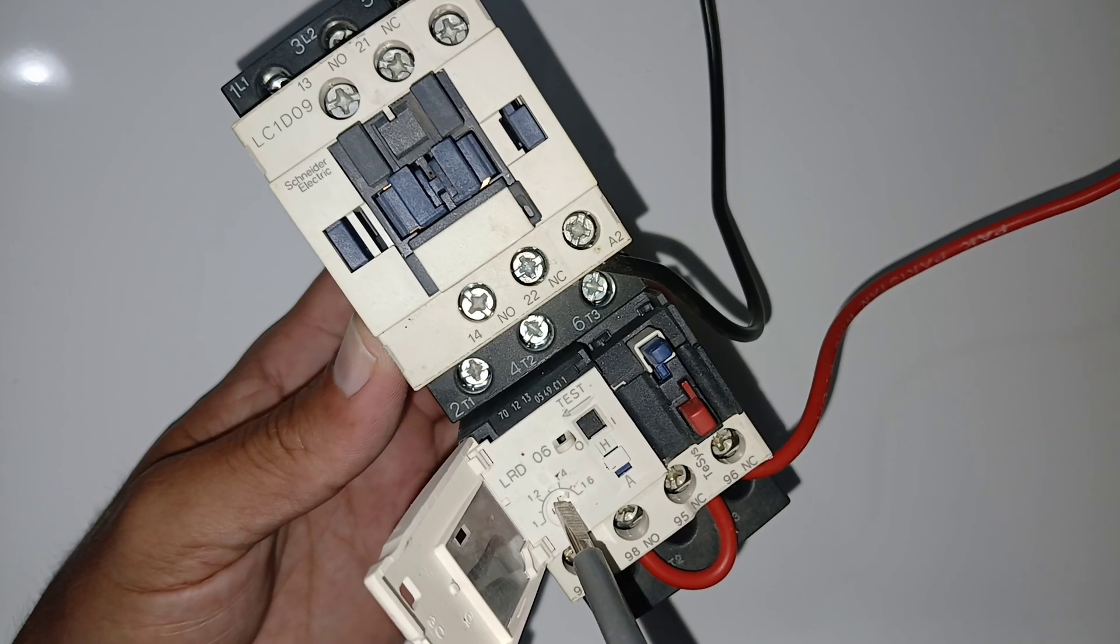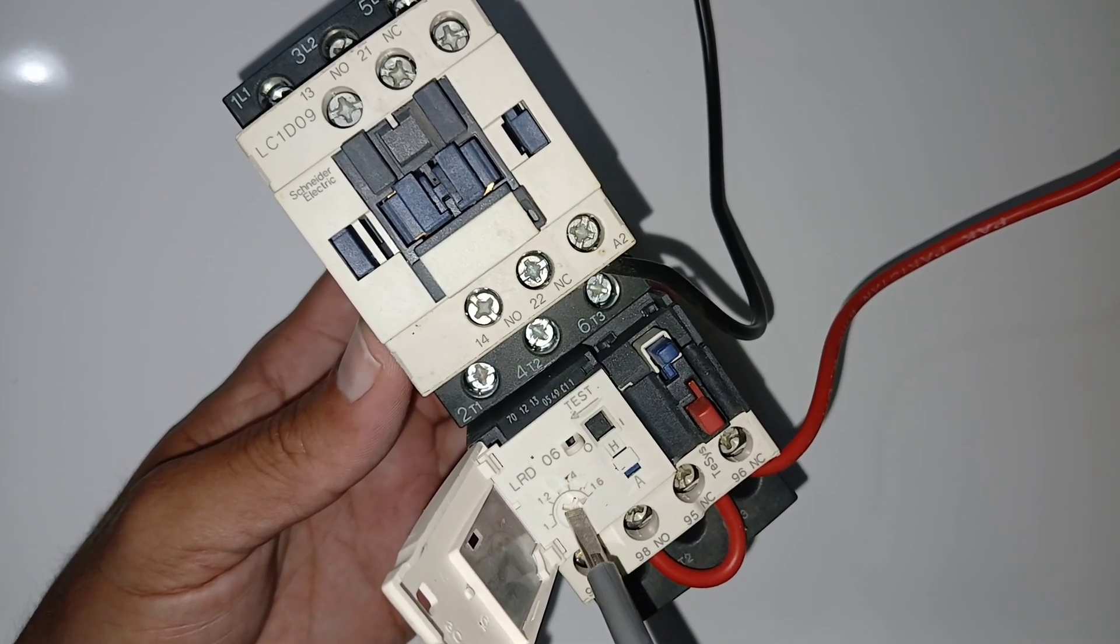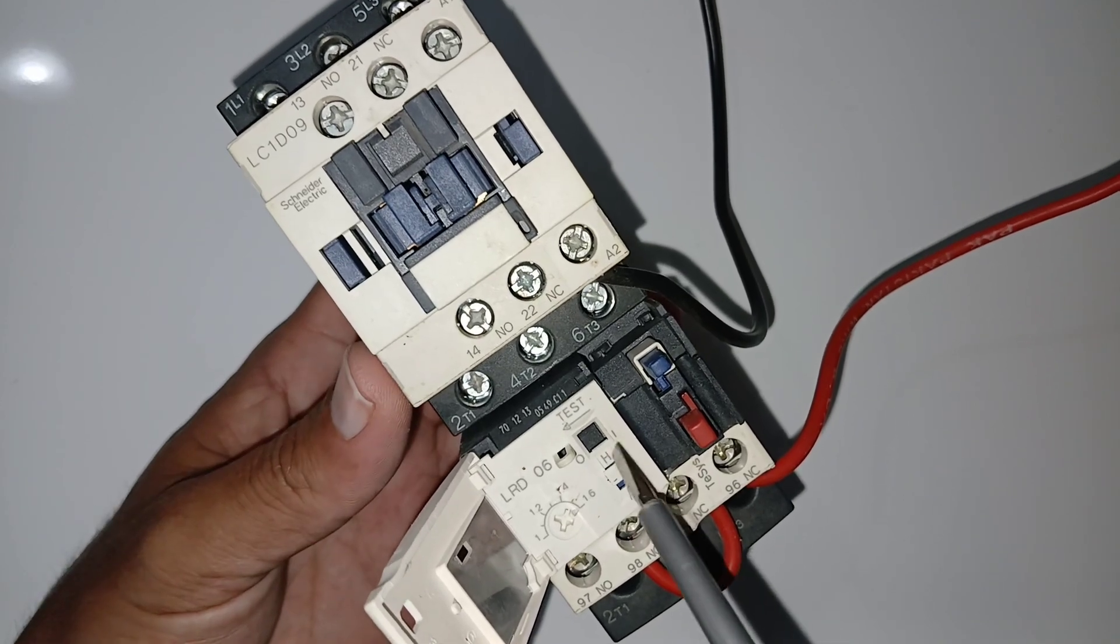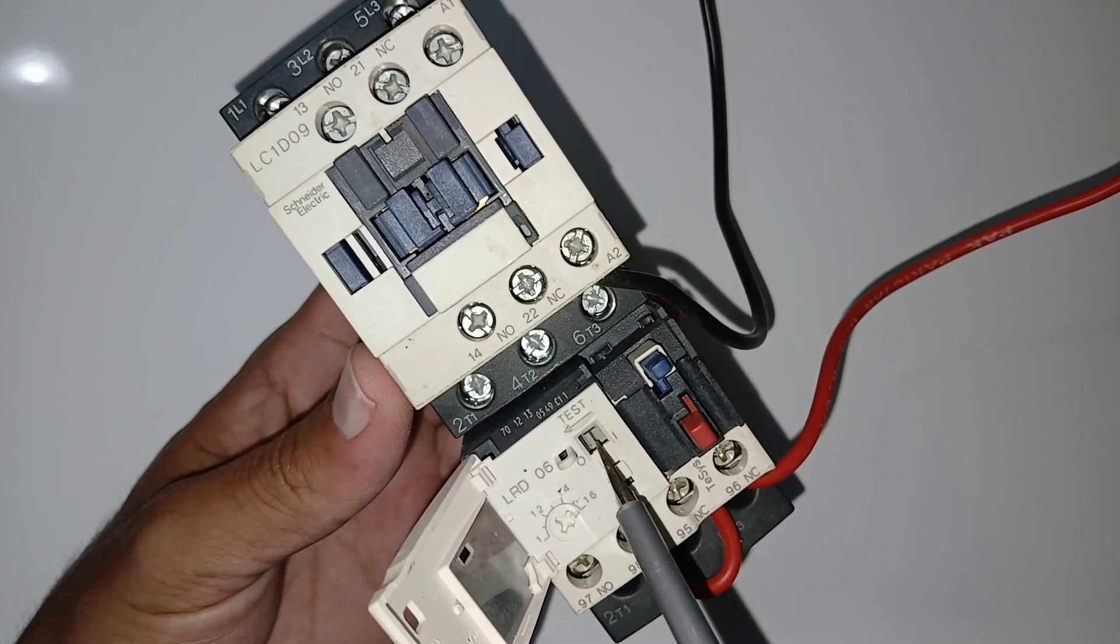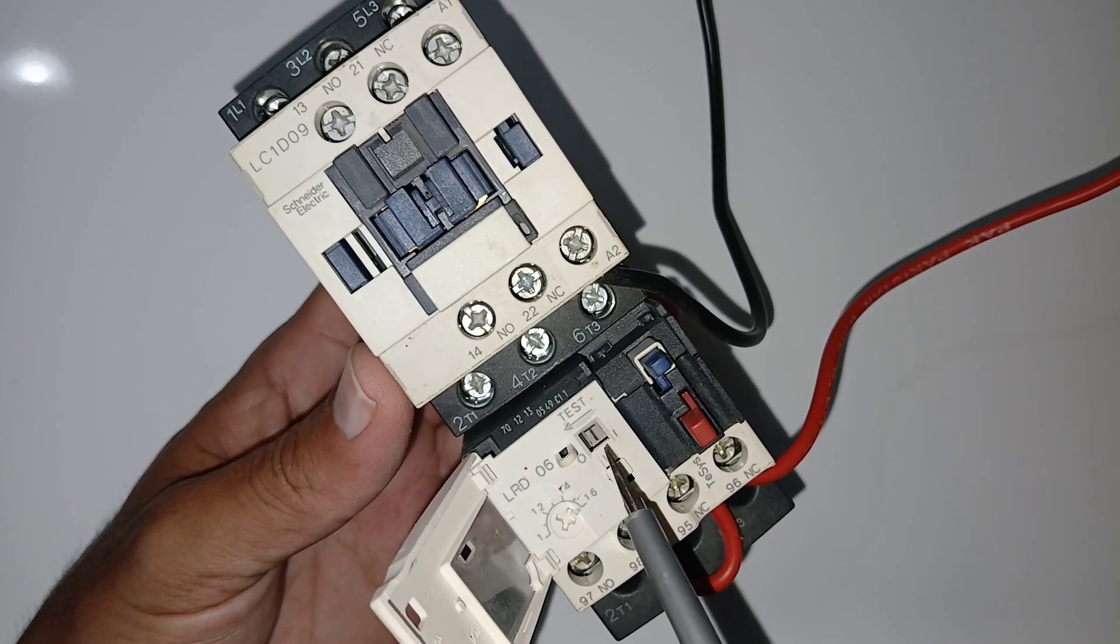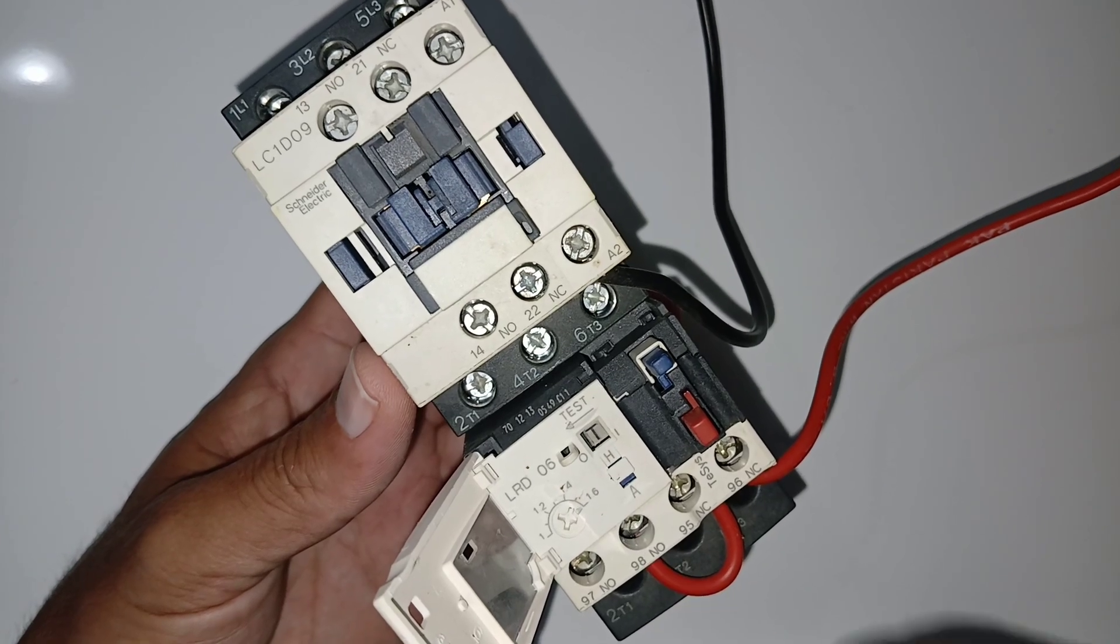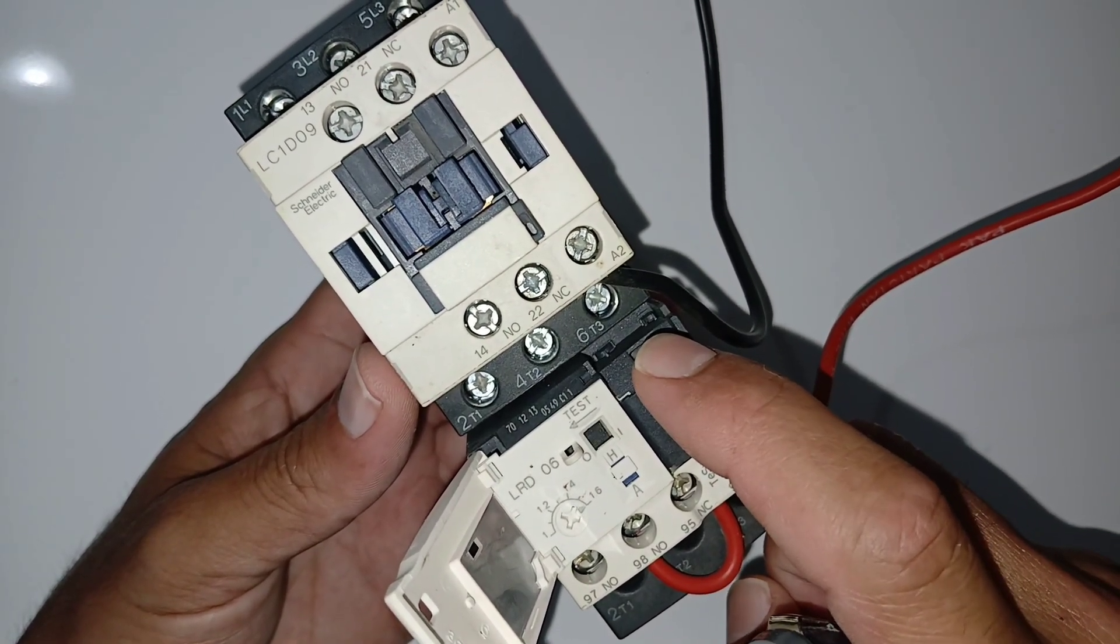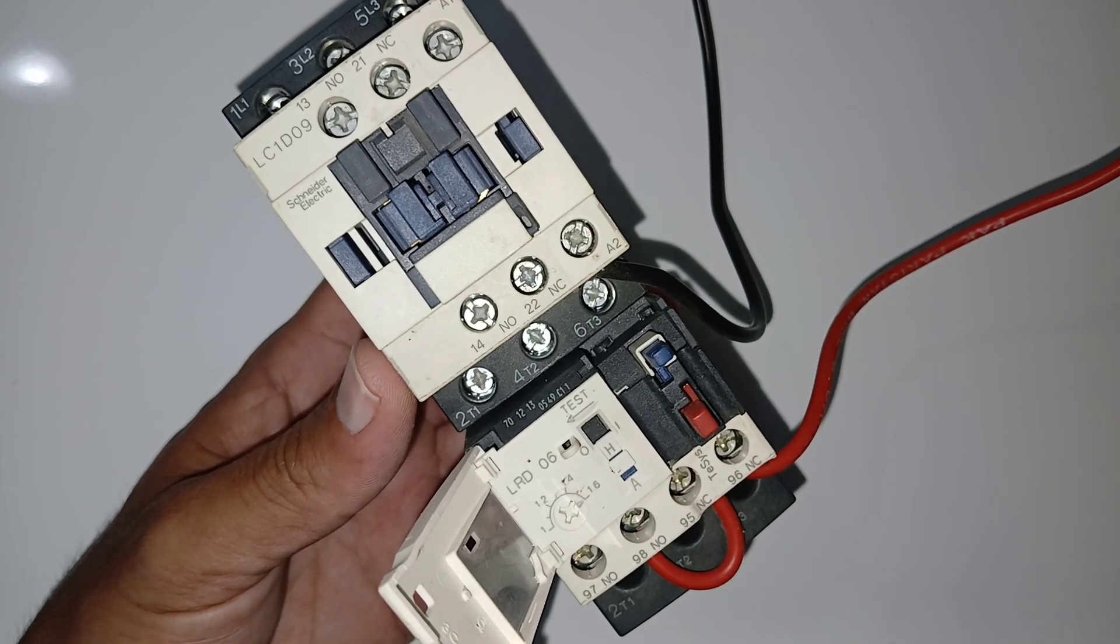1.2 here, you can set like that, 1.5. So this one is ampere setting, and this one you can see, test button. You can test if you want to check the overload relay is okay or not. For example, I put on test. Now I will reset. You can see, this is working now.